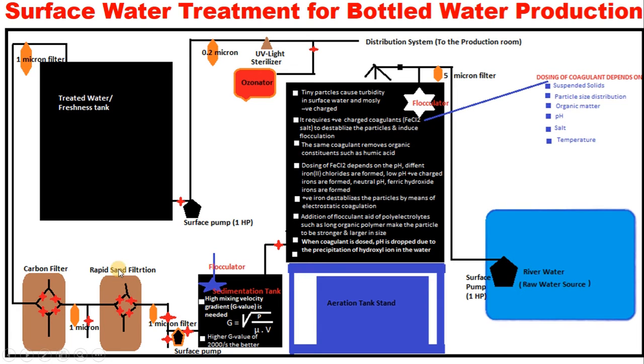If the bed depth law is not maintained, the high pressure will break the sand particles into tiny particles that will flow through the line, which will contaminate the water along the line. So now, if everything is done, coming to this point, this is another sampling point where turbidity is measured to know whether this rapid sand filtration would have dealt with the turbidity.